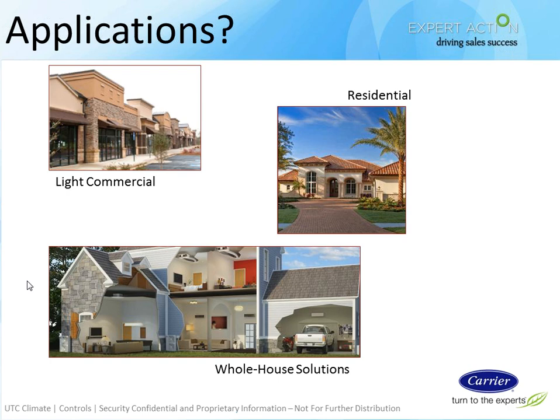Where can duct-free systems be used? Pretty much everywhere. It ranges from light commercial to residential to whole house solutions and up to some pretty strong commercial applications as well. This equipment blurs the line between residential and commercial markets, provides an entryway for residential contractors into commercial and vice versa. Heating can be a challenge, but heat pump technology is improving year by year. And with the product that we'll be talking about today, testing is currently taking place to achieve good heating performance down to minus 13 degrees Fahrenheit. This, of course, helps with whole house solutions.